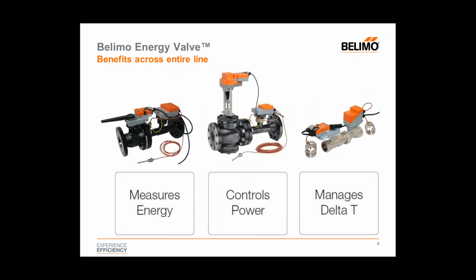As we talked about before, we have temperature sensors on both the supply and the return of a coil. So now we have the ability to measure BTUs. Flow times 500 times delta T gets us to BTU measurement. That BTU measurement can be used for various applications. It could be used for monitoring to understand how much consumption a particular air handler is using.